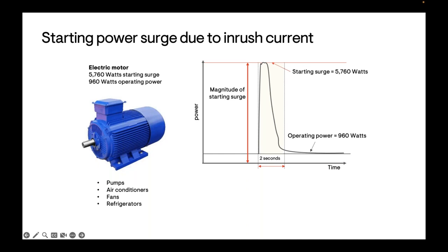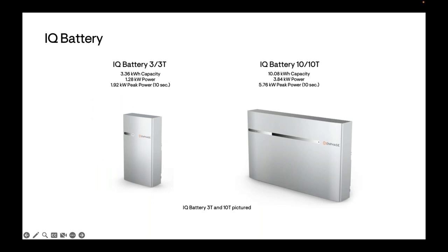Here are the two battery sizes we offer as building blocks. The IQ Battery 3 is the smallest, with 3.36 kilowatt hours of energy capacity and a power output of 1.28–1.92 kilowatts. The IQ Battery 10 is essentially three IQ Battery 3s connected together under one large cover. Because the system is fully interconnected, the energy and power numbers are additive — multiply the IQ Battery 3 numbers by three to get the IQ Battery 10 specs, and the same logic scales all the way up to 40 kilowatt hours.